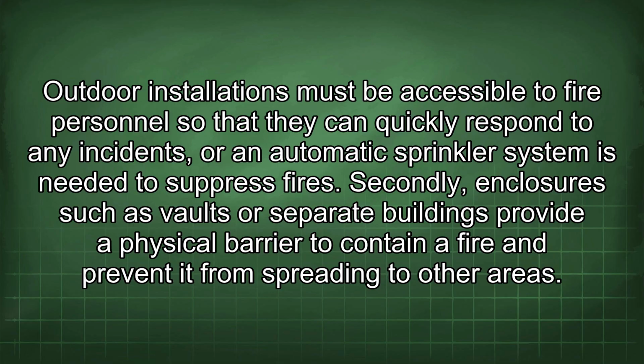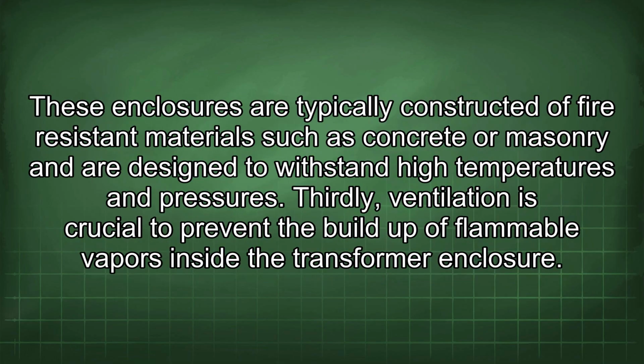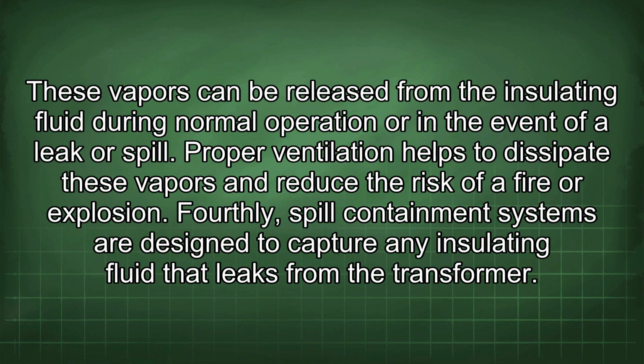Secondly, enclosures such as vaults or separate buildings provide a physical barrier to contain a fire and prevent it from spreading to other areas. These enclosures are typically constructed of fire-resistant materials such as concrete or masonry and are designed to withstand high temperatures and pressures. Thirdly, ventilation is crucial to prevent the buildup of flammable vapors inside the transformer enclosure. These vapors can be released from the insulating fluid during normal operation or in the event of a leak or spill. Proper ventilation helps to dissipate these vapors and reduce the risk of a fire or explosion.